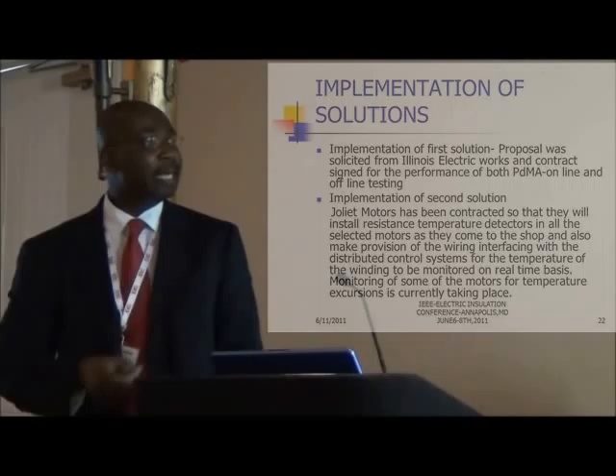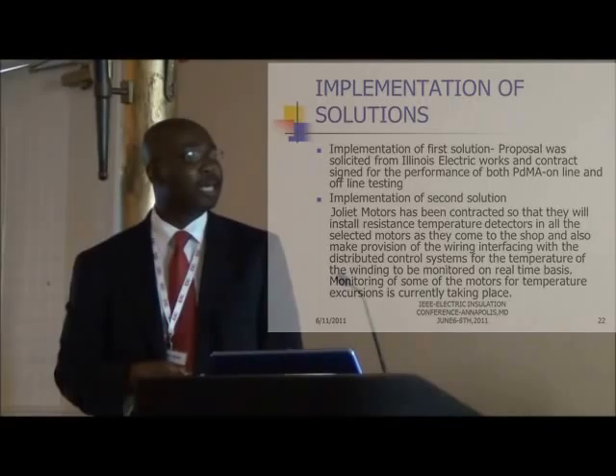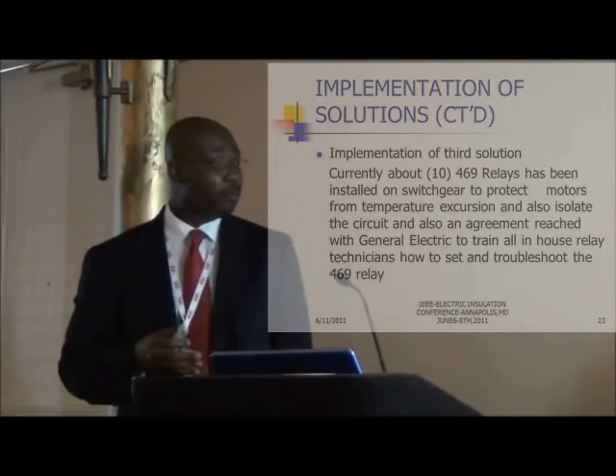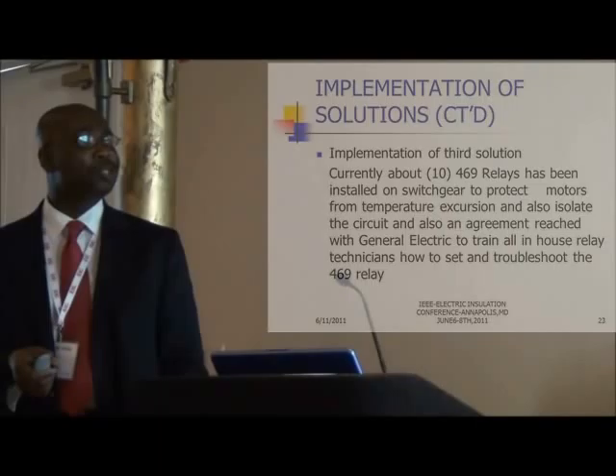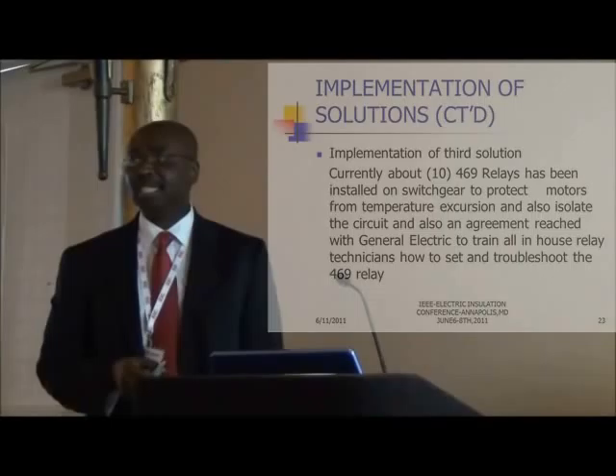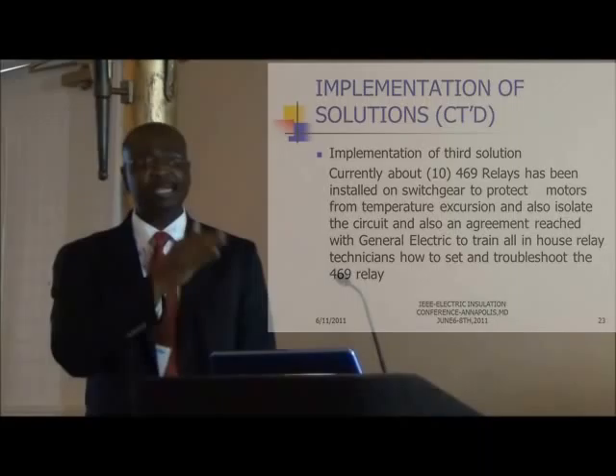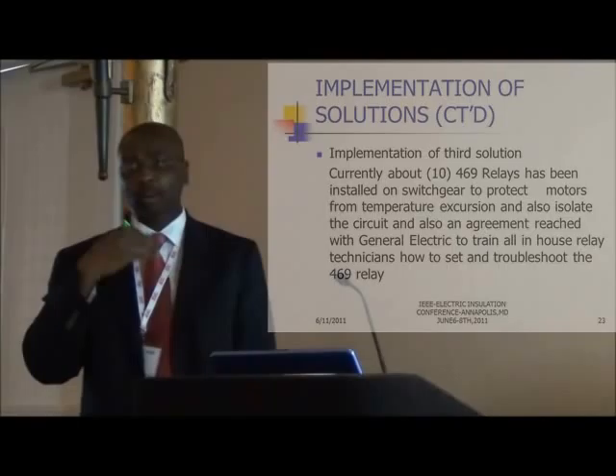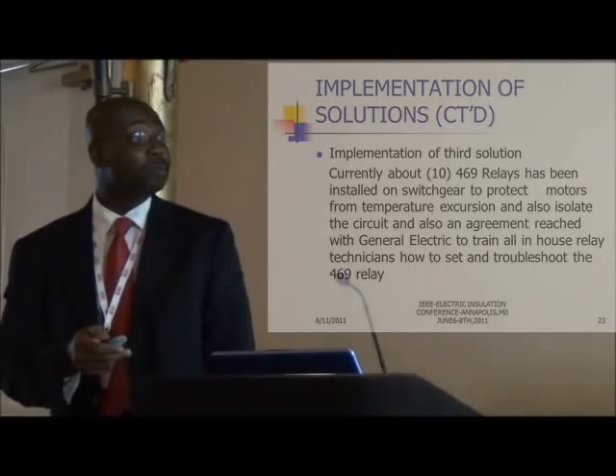We also implemented the installation of RTDs during motor rewinds, and installed 10 GE 469 multi-function relays in the switchgear. The multi-function capability provides good temperature monitoring and indication of any temperature excursions. The RTDs can be wired to the DCS in the control room so operators always have visibility into motor condition and can take early troubleshooting action.